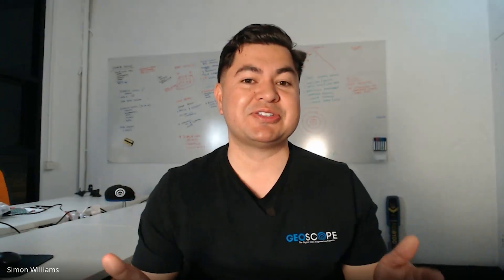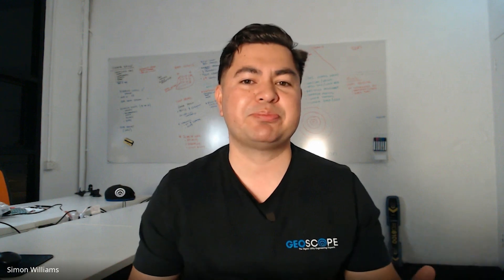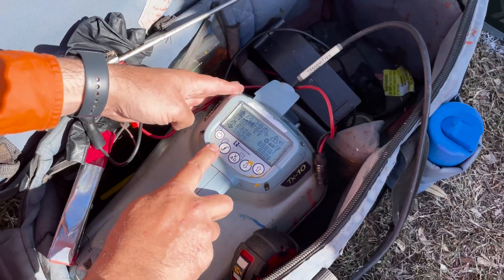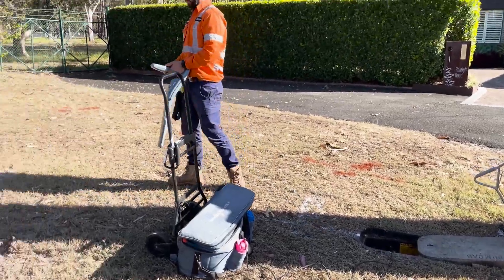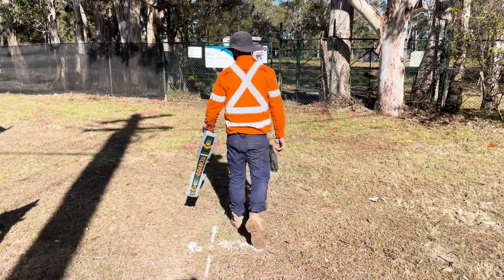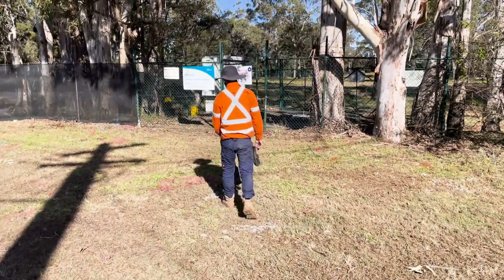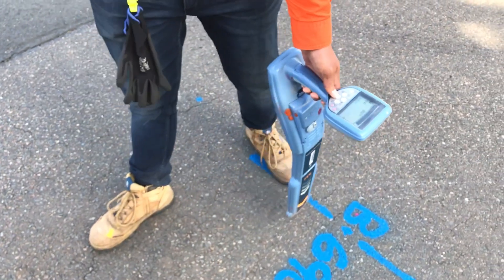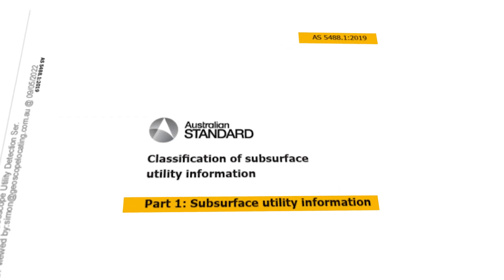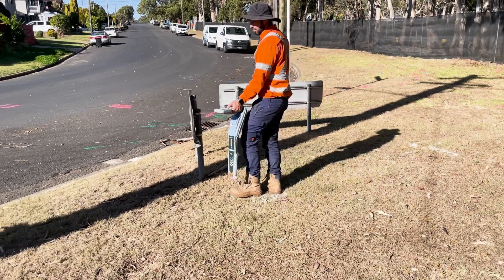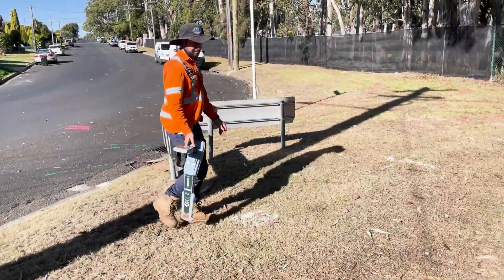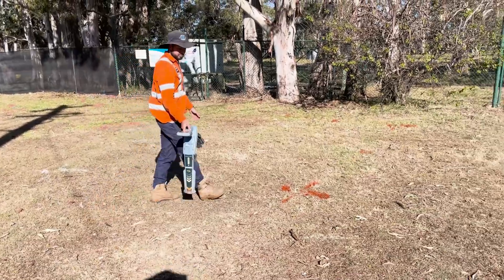Every location we go to requires a strategic process to complete the job efficiently — some jobs are easier than others, and you never quite know what you're going to get until you start scanning. Just because we've located this cable with power mode using a passive locating method doesn't mean we've accurately located the cable. When it comes to the Australian Standard AS 5488, passive locating or power scanning methods are not classified as a Quality Level B (QLB) locating method, as we have not used active locating methods to trace these cables.